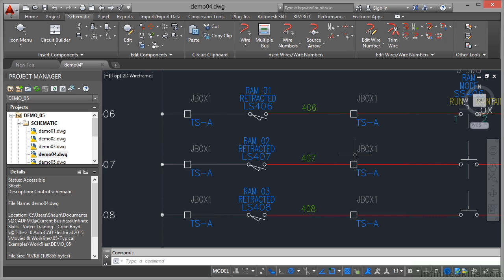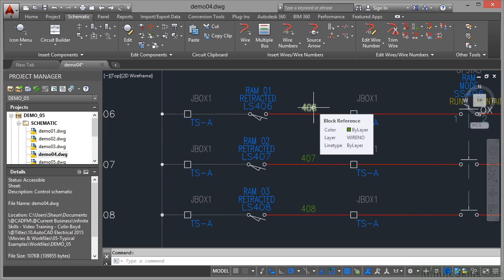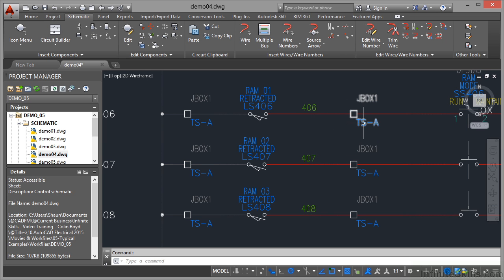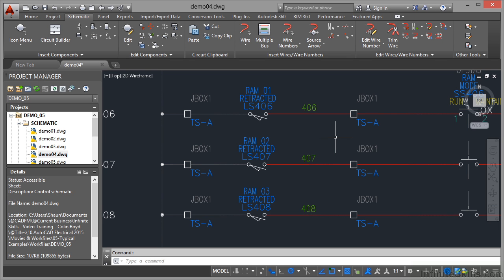You must use the editing tools in AutoCAD Electrical though. This is all linked to the AutoCAD Electrical database and you must use the tools provided. Don't just go in and use the AutoCAD text editing tools to change a wire number or junction box number, and don't explode the blocks either because they are all linked, automated with parametric tools and block attributes and so on. The whole idea of this is to make your life easier. You will make your life much more difficult if you explode things in a typical AutoCAD Electrical drawing.